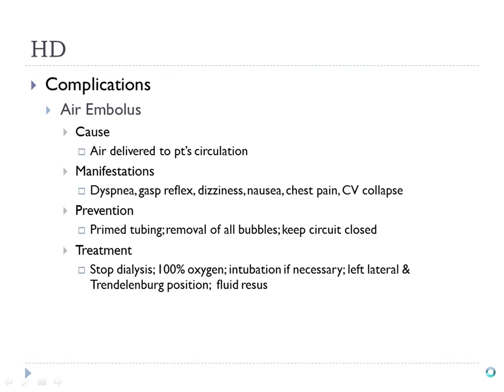Make sure tubing is well-primed with no excessive bubbles, and that the circuit system of tubing remains closed. If an air embolus occurs, the first thing you do is stop the dialysis and give the patient oxygen. They may require intubation. Position the patient in left lateral Trendelenburg to prevent air from moving into the circulation and keep it trapped in the ventricle.